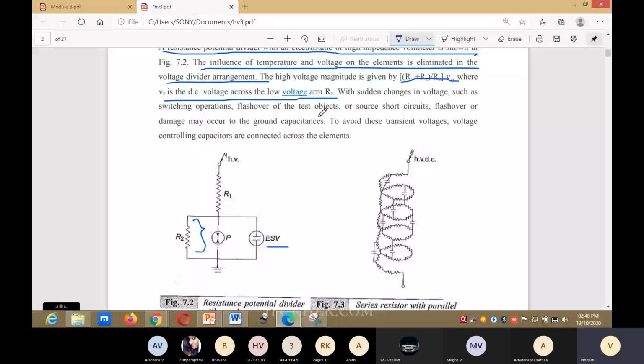With a sudden change in voltage, such as switching operations, flashover of the test objects, or a source short circuit, flashover or damage may occur to the ground capacitance.